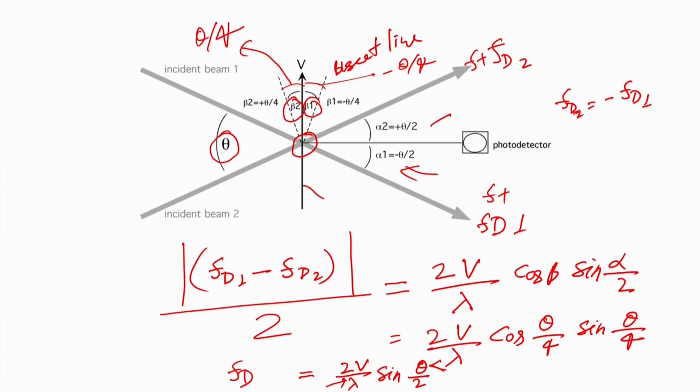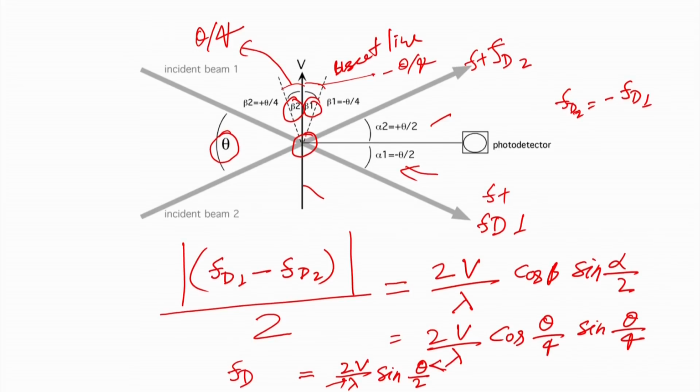Now, if you subtract this, you will get FD2 minus FD1 or FD1 minus FD2. We know how much scatter there will be; that just depends on the direction. The direction will be opposite, and that is why FD2 will be equal to minus FD1, and we calculate the FD. So, this gives you higher sensitivity, and better accuracy is observed in the dual beam compared to the single beam. The formula remains the same. You use these values to calculate the FD value here.